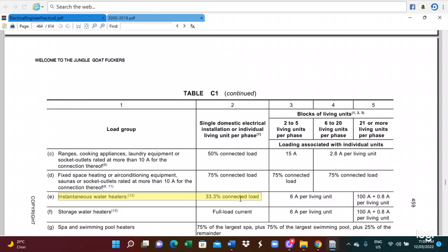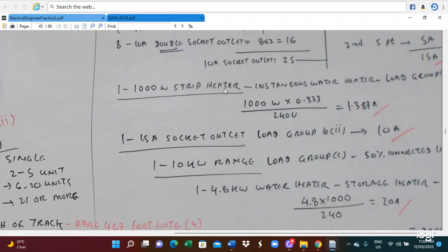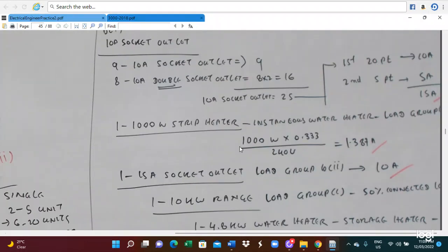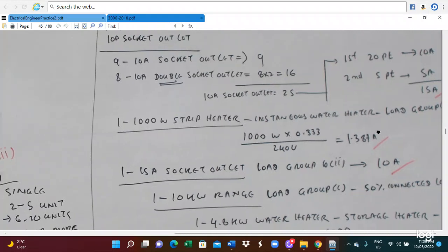So we take the 33.3% of the connected load. So 33.3% of the connected load we calculate that. So the 1000 watts, so 1000 multiplied by 0.333, you get the watts. So this is divided by the voltage of 240. So you get 1.387 ampere. So this is for the 1000 watts of strip heater we calculated.